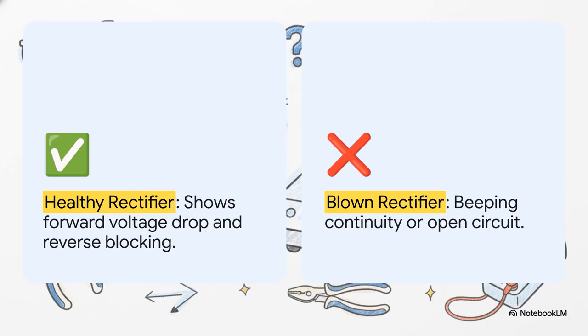Next is the bridge rectifier. Switch your multimeter over to diode mode. A healthy rectifier has an internal network of diodes, so if you probe the center AC input pins and the outer DC output pins, you should see a standard forward voltage drop of about 0.5 volts in one direction and total blocking, meaning an open circuit when you reverse the probes. A blown bridge rectifier will either beep at you with a dead short, or it will be completely open in both directions, which basically means the internal diodes have literally blown apart.